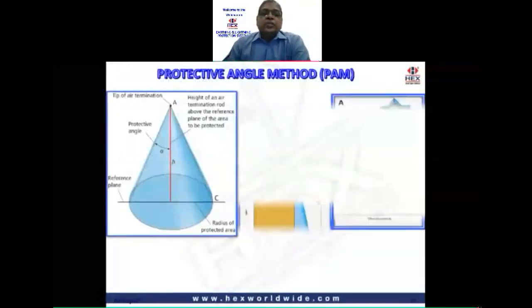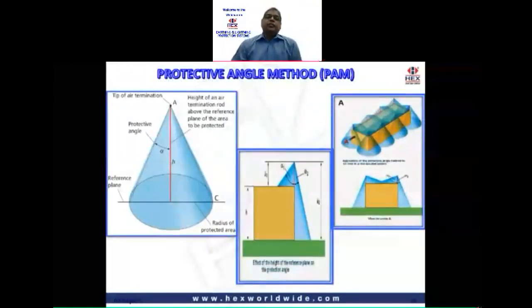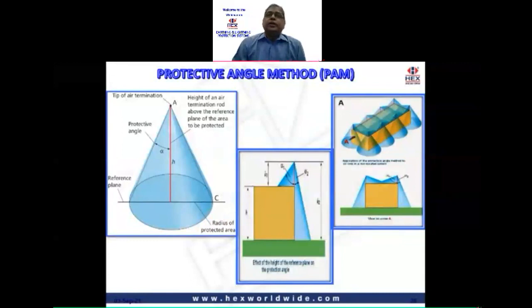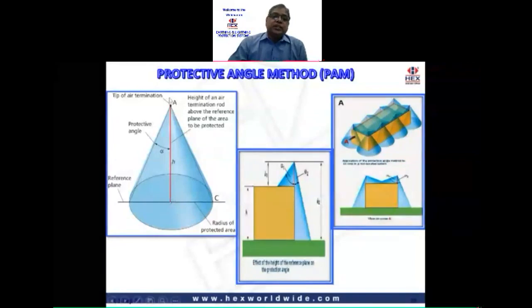Now, getting on to the last method, that is the third method, the protective angle method. This method gives the angle that must be used to design the lightning protection system. The cone that is formed, this is the cone, as you can see, which is formed here. This is the lightning arrestor, and the cone is formed as per the particular angle which is given in the standard.